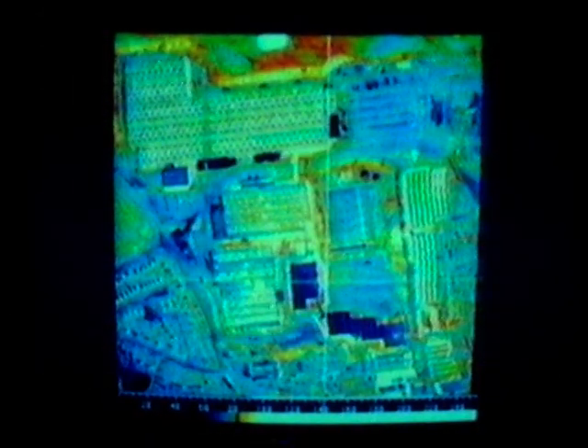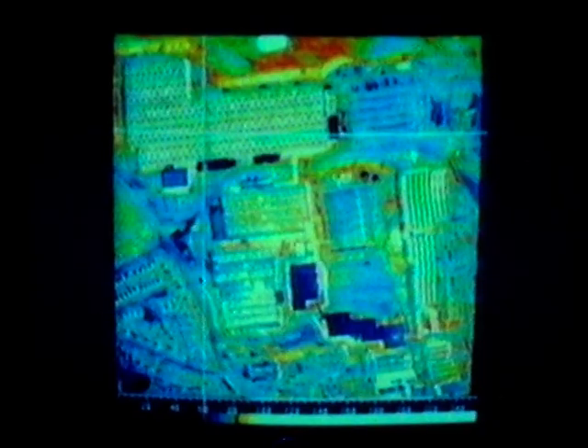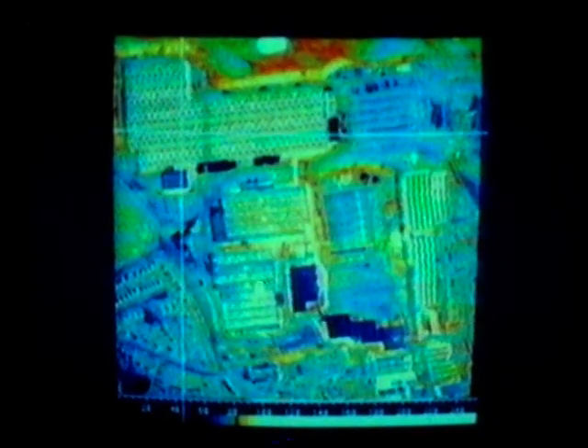And can we look now at the roof of the factory over there? I can see some hot spots there. Yes, this is quite a warm building here. You can see the lighter areas along here. That's probably heat loss through vents. It's difficult to know until an on-site investigation is made, but the energy manager could investigate the matter on-site. Aerial thermography helps to track down those parts of the building where the heat insulation is inadequate.